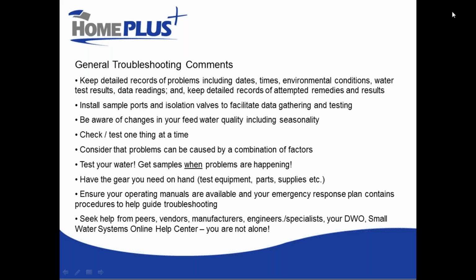Obviously, be aware of changes to feed water quality and how that might affect your treatment processes, and seasonality will be a very big one there. So don't be too surprised, for instance, if you see heightened turbidity during spring freshet, and that may have an impact on your equipment.